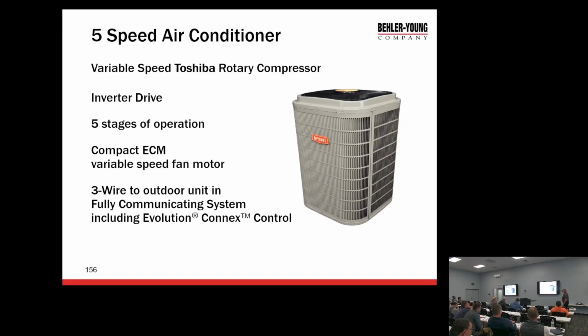Like I was saying earlier, this is the 5-stage compressor. This has now been changed to a variable speed. This is now the 290. So the 288, which was a 5-speed, is now full variable speed. Okay, but this has an inverter in it, just like a mini split. It has those capacitors. It holds all that voltage.